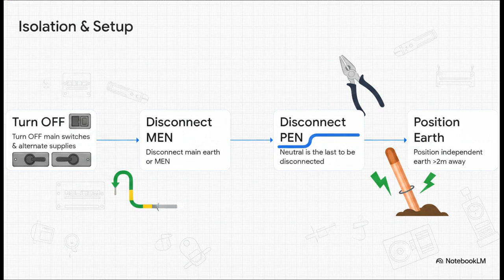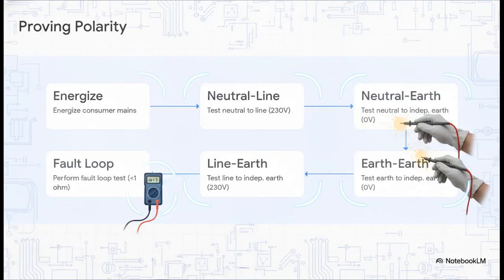The absolute golden rule here, say it with me, is that the neutral conductor is always the last to be disconnected and the first to be connected. Finally, drive your independent earth stake into the ground at least 2 meters away from any other conductive surfaces. Now let's see how this builds into the active testing phase.